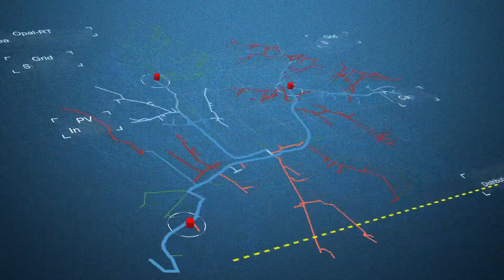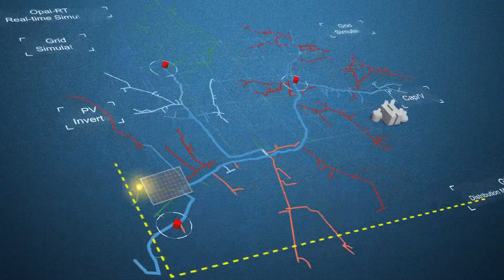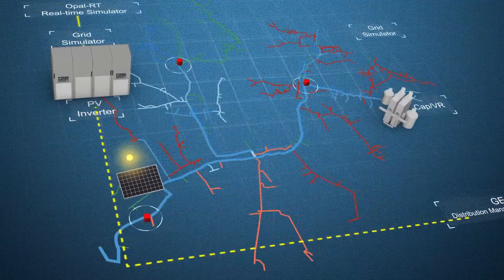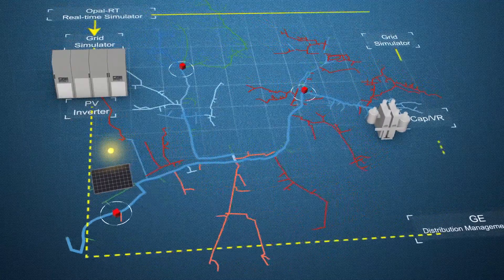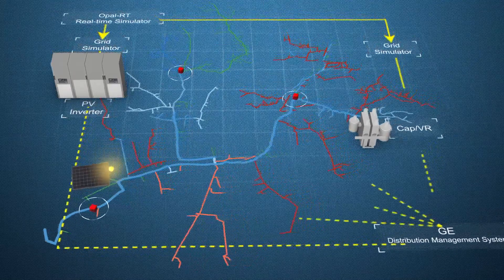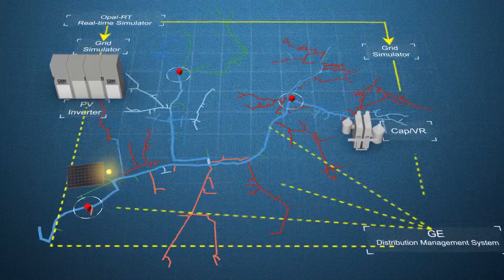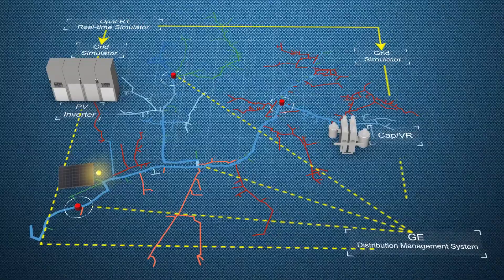We wanted to make sure that what we were simulating matched reality, so we took advantage of the unique capabilities of ESIF to have actual hardware — a real advanced inverter in the lab — interacting in real time with the distribution management system. This validated that we were capturing the advanced inverter properly in the models we used for the longer simulations.